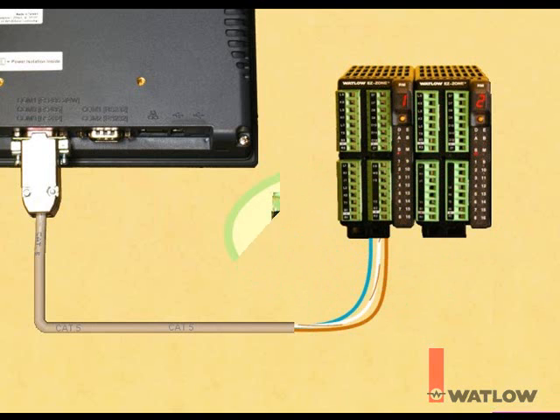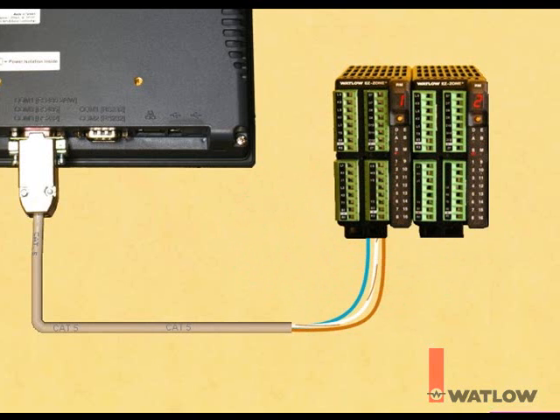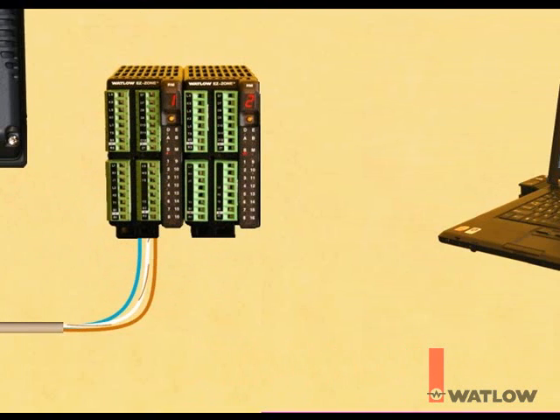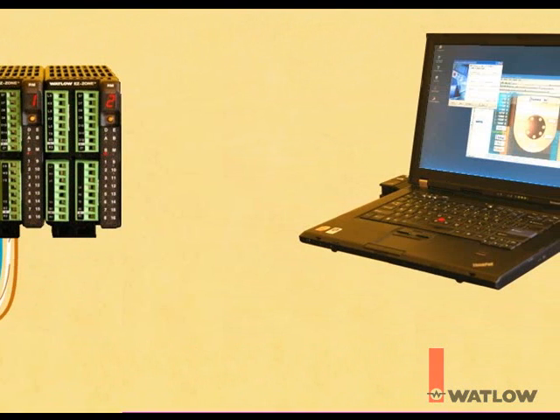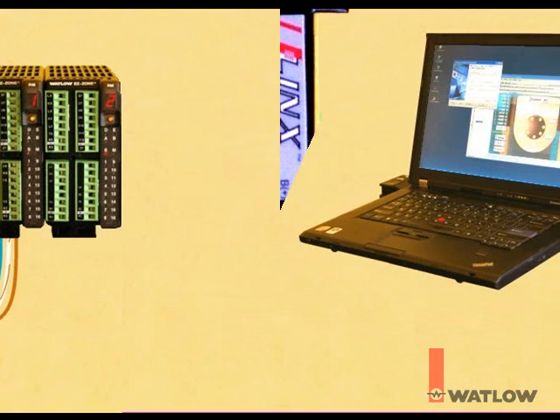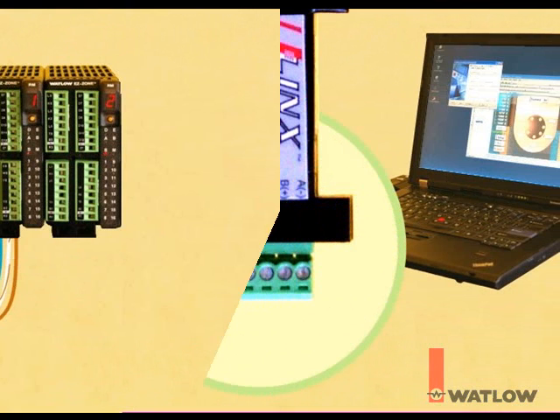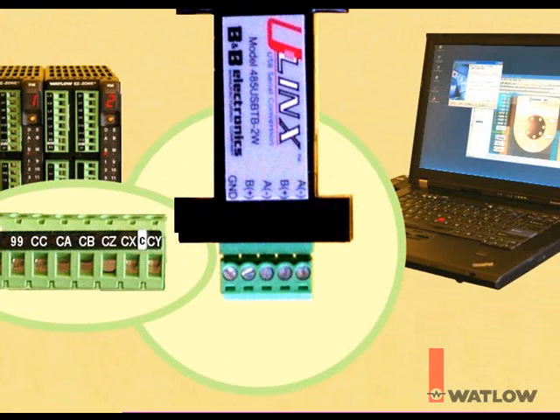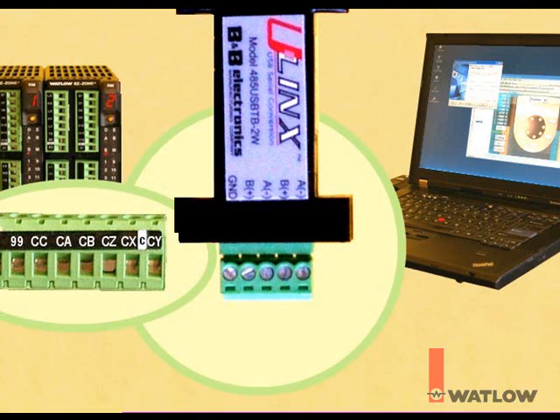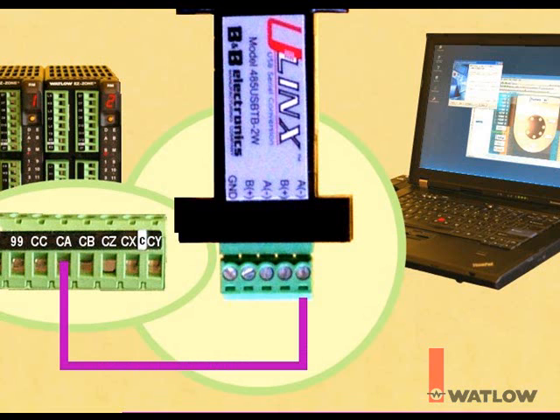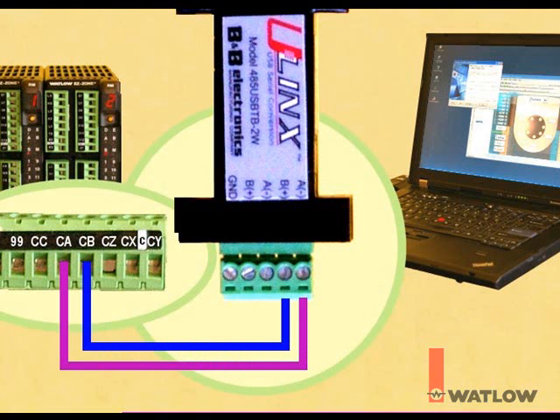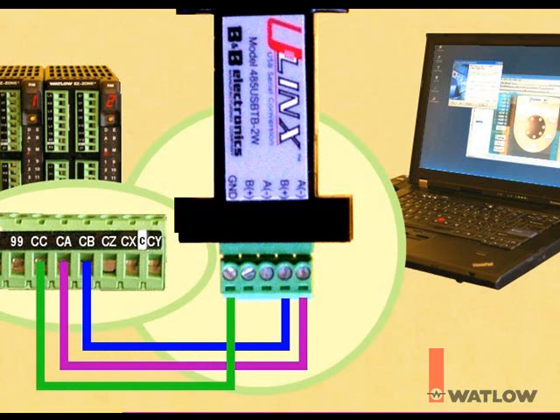Let's also make a connection from the PC to the other RM in the system. If you have the USB to 485 converter available from Watlow, use one pair of wires in a shielded twisted pair communications cable to connect CA on the RM controller to either of the A terminals on the converter, and CB on the RM to either of the B terminals on the converter. Using a wire from a second pair, connect CC to ground.